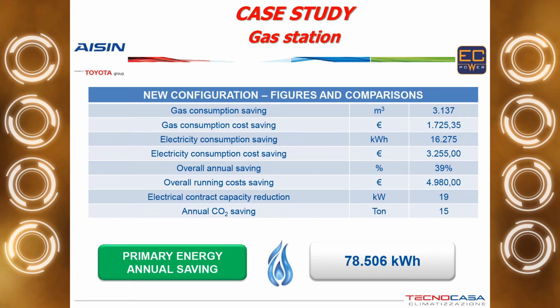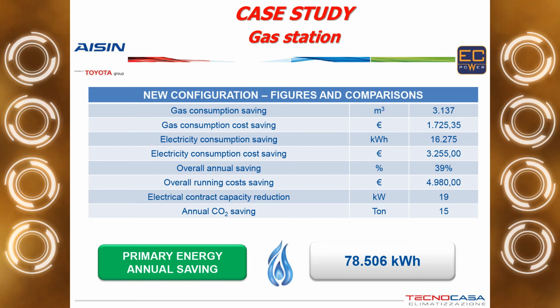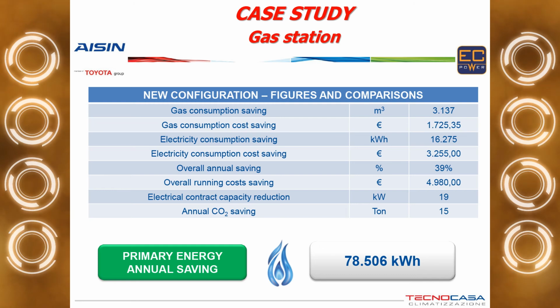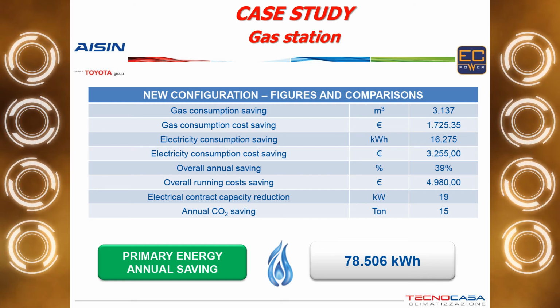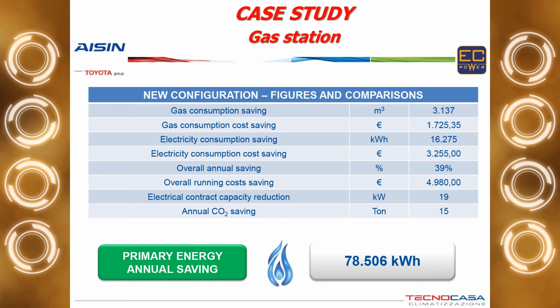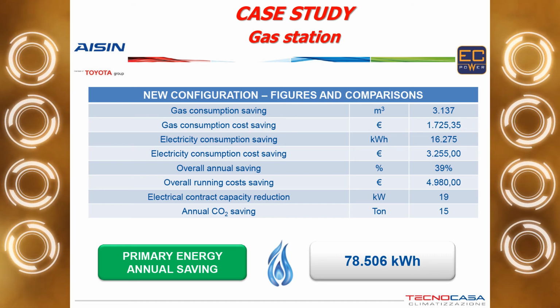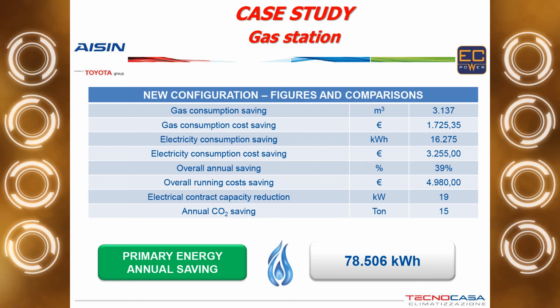So let's compare the figures. We had a gas consumption saving from one year to the next one of 3,137 cubic meters of gas, which means something around 1,800 euros. And we also had 16,275 kilowatt hours of electricity that we didn't use. So something about 3,255 euros. All in all, the running cost saving of the gas station was almost 5,000 euros, which is about 39% compared to the year before.